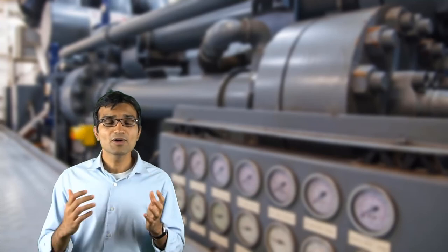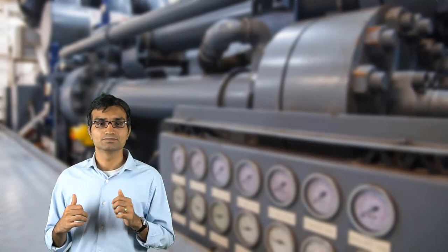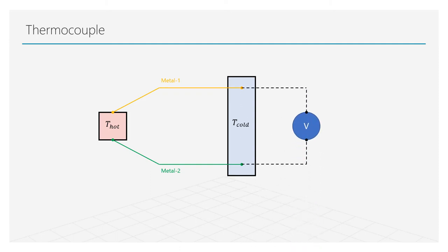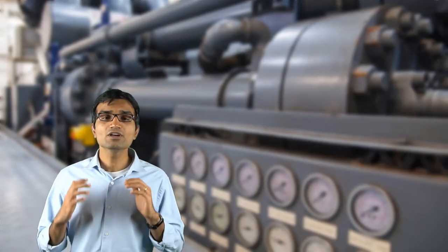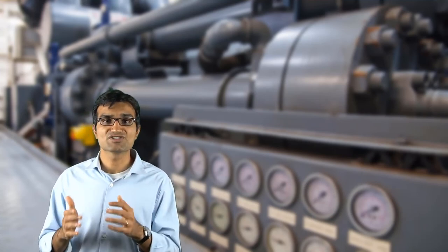A thermocouple, on the other hand, operates on the principle of Seebeck effect. Two different metal strips produce an electromotive force or voltage when there is a temperature gradient between them. The thermocouple senses this voltage and passes it to a data logger which provides the final temperature reading. It is important to note that these temperature measuring devices only provide a point measurement.